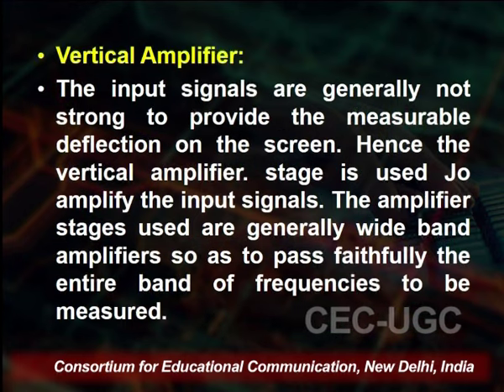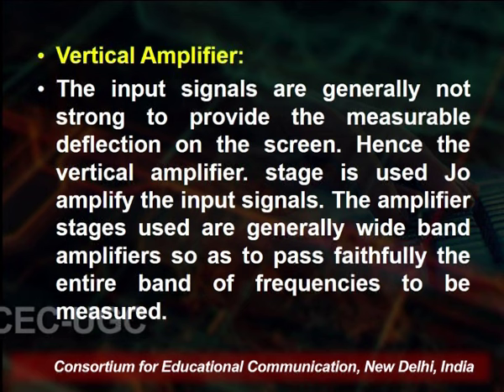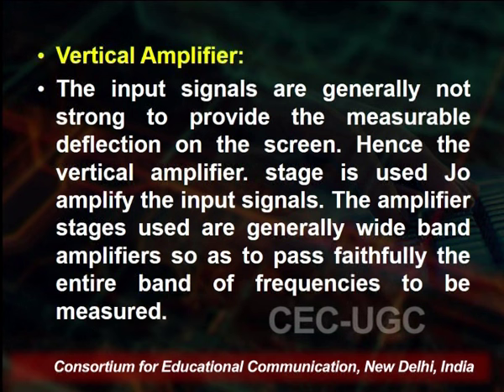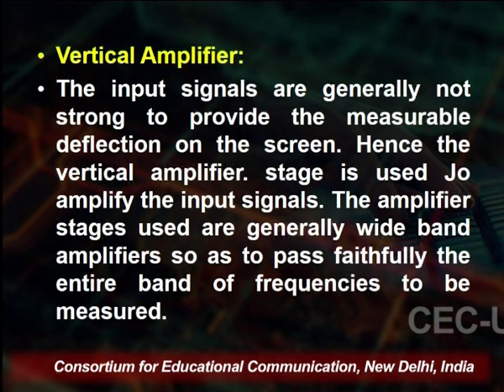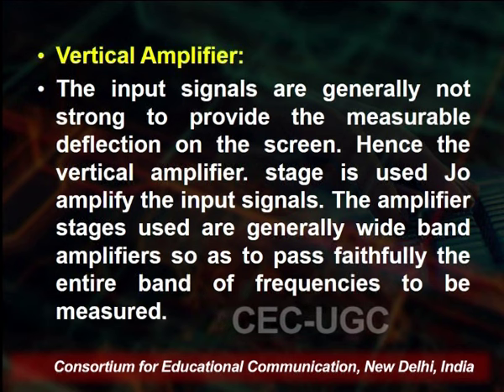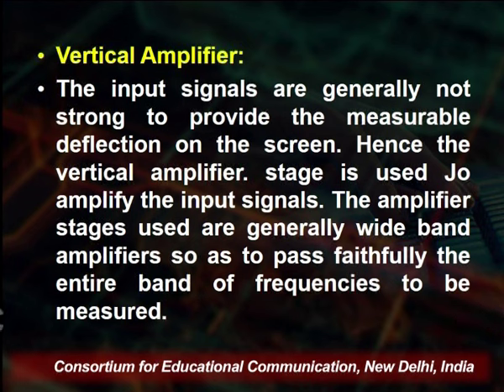The next part is the vertical amplifier. What is the purpose of this vertical amplifier? The input signal is not generally strong, so to provide a measurable deflection on the screen, through this vertical amplifier we get a strong signal — we can amplify the input signal so that we can get the amplified output.